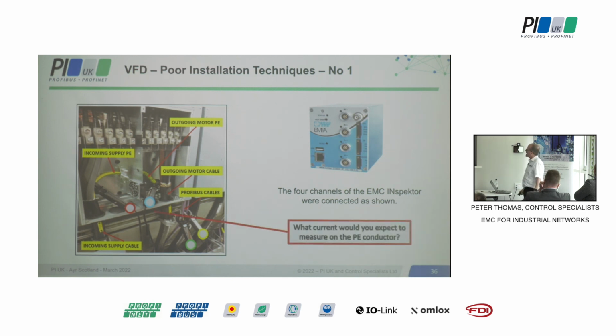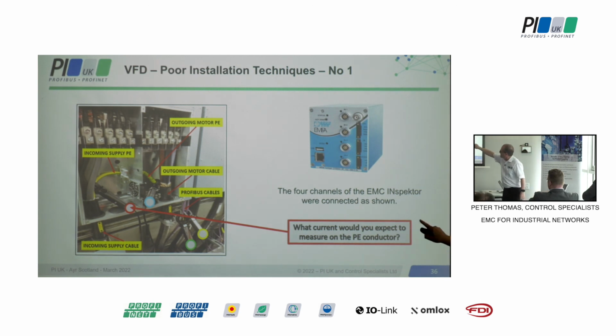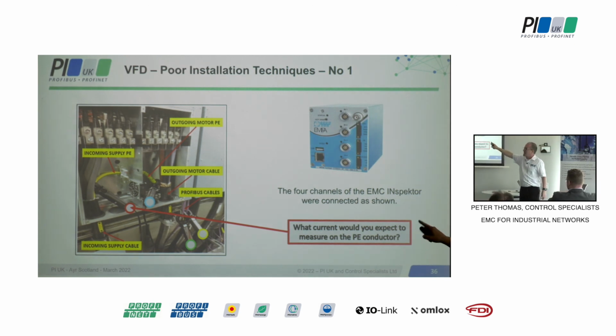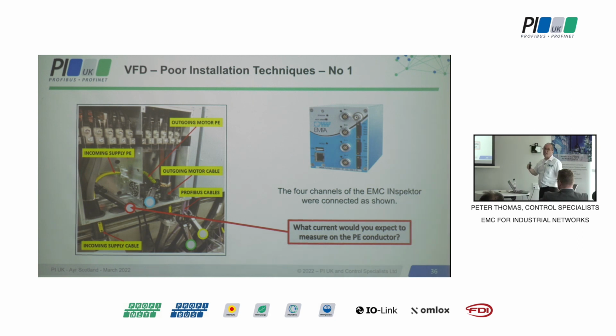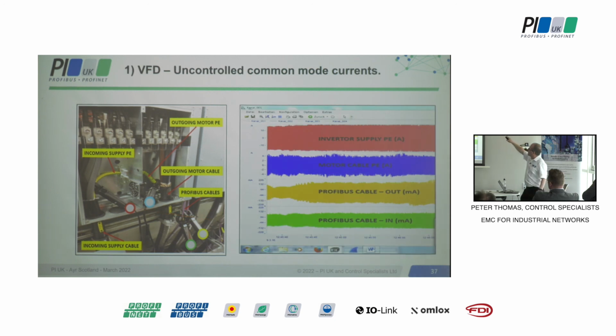The question I ask everybody is, what would you expect to see on that clamp there - the red clamp clipped over the green and yellow protective earth wire? Most say zero. Some might say a few milliamps, something like that. Well, what you're going to see now is typical of a drive that hasn't been installed in line with the manufacturer's guidelines - and I've seen this many, many times. Look at the top: 12 amps in that PE.